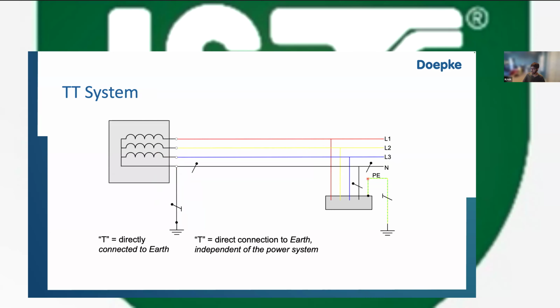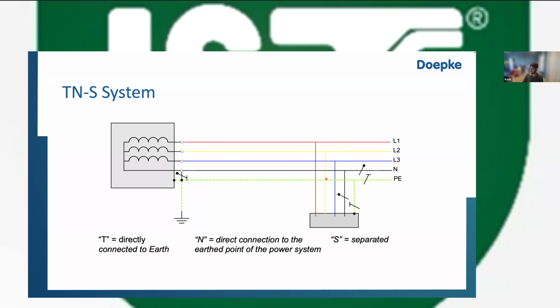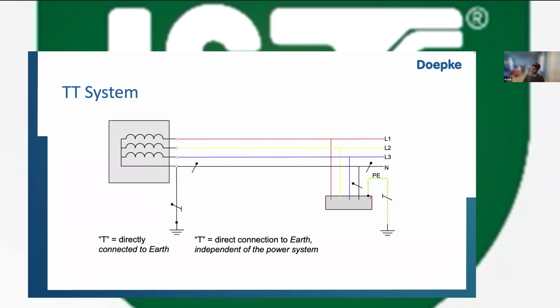But unlike there being a protective conductor back to the source, which is what we have here, you have a connection of the exposed conductive part directly to the general mass. And this is when you have a small problem. The problem mainly is that if you have an earth fault between the line conductor and the protective conductor, or the line conductor and the body vehicle, the amount of fault current is limited by the resistances of these electrodes and the actual soil between.